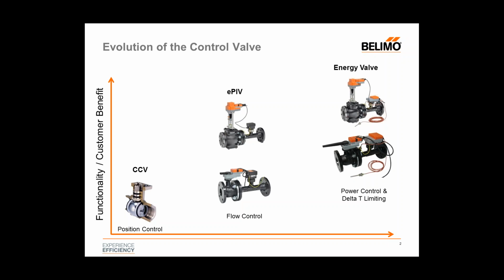What it helps to do is maintain the coil design at a specific delta T set point, for example, 10 degrees. So if the coil is set for 10 degrees, the energy valve would modulate flow through that valve to maintain that design 10-degree coil delta T. And as I said, we're going to talk a little bit more about that in the subsequent slides. We also have separate webinars available for power control and for delta T management. So if you'd like an even finer in-depth understanding of those, we recommend you check those out as well.